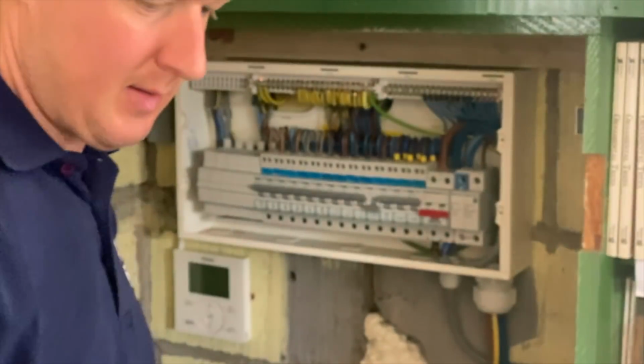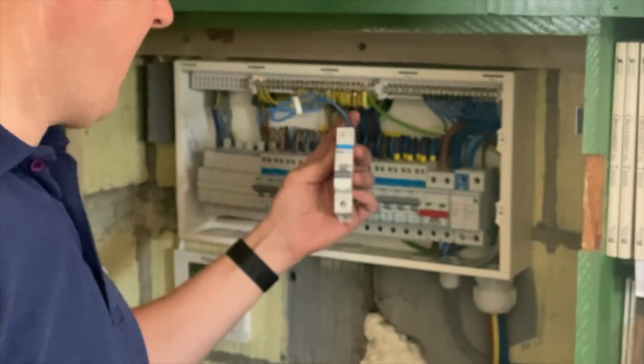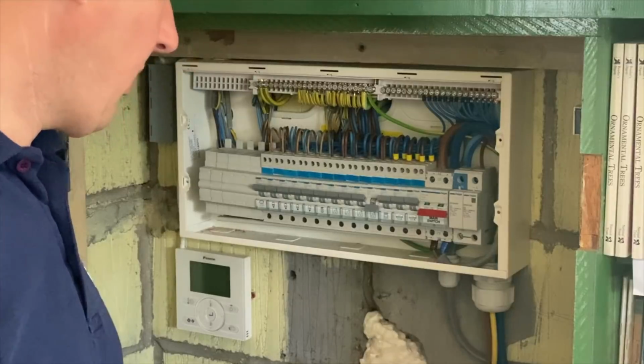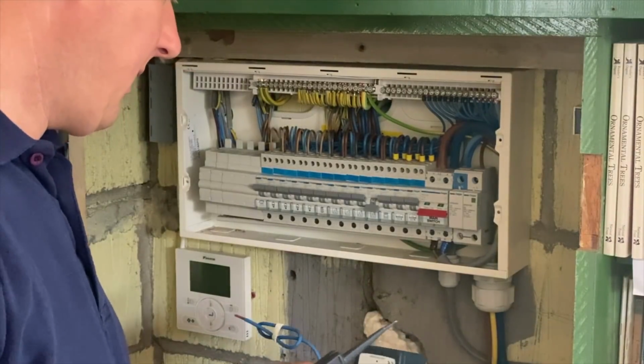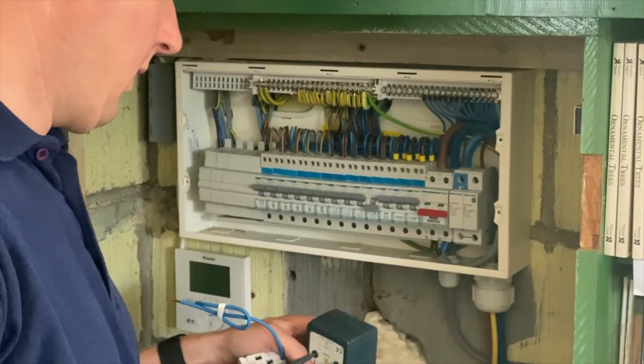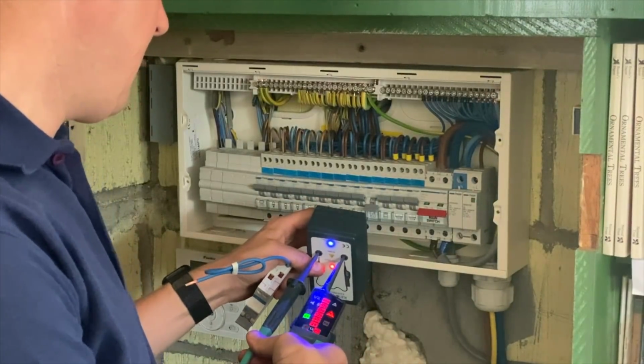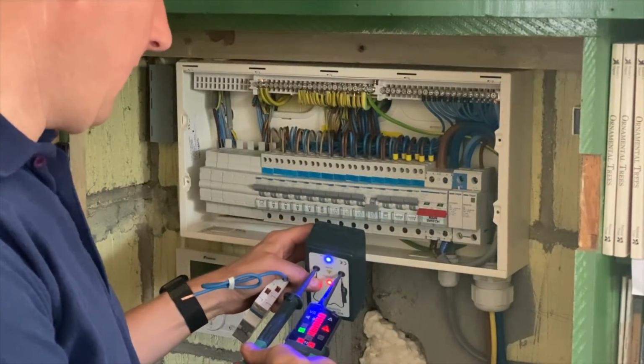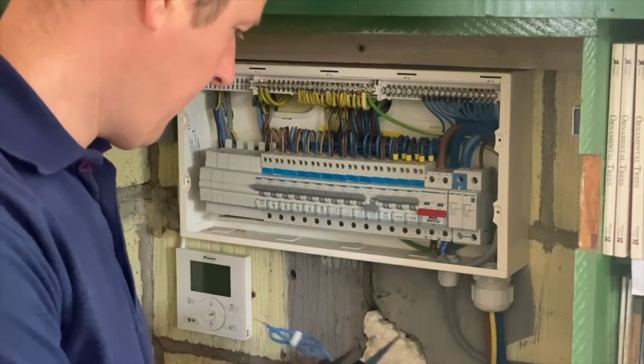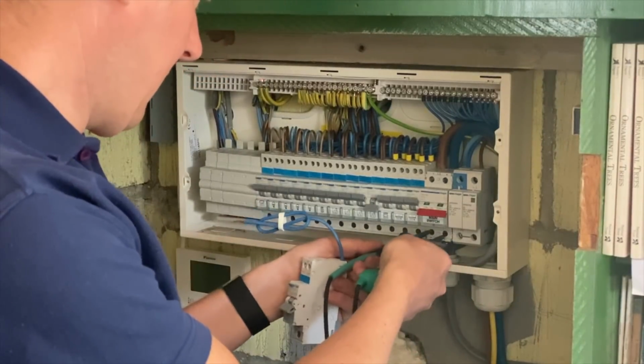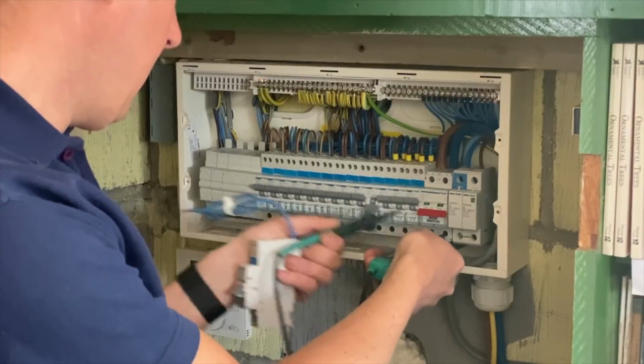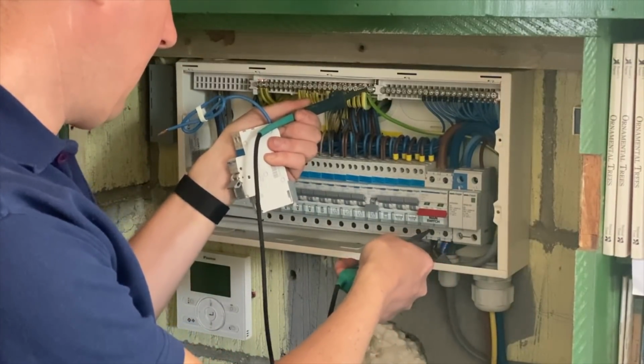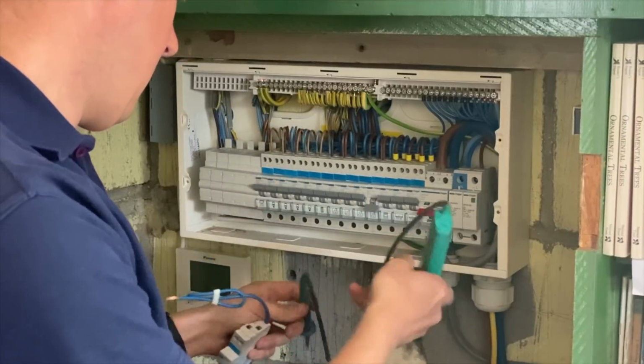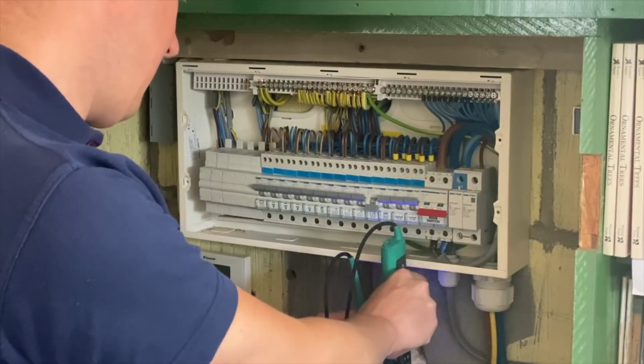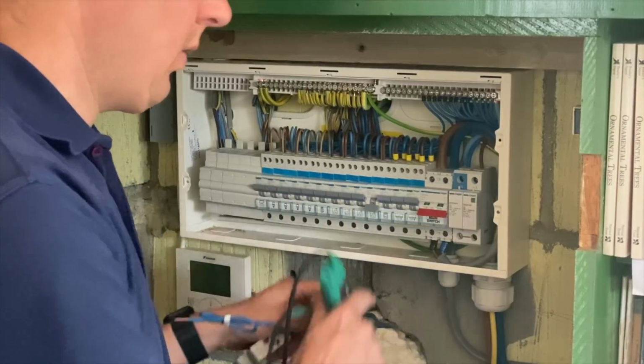Fortunately, because I do a lot of Hager installations, I do carry some spares, and I've got a spare 32 amp breaker there. So I've just turned off the main switch, but I'm just going to check to make sure that everything is dead before I start taking the bus bar out or disconnecting the breaker. So just going to test on the outgoing side of the switch, and that is fine, that's all dead. And then I'll just prove that it's dead by checking my tester again. All good.